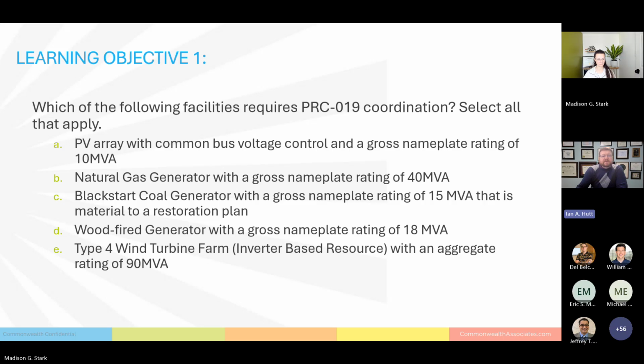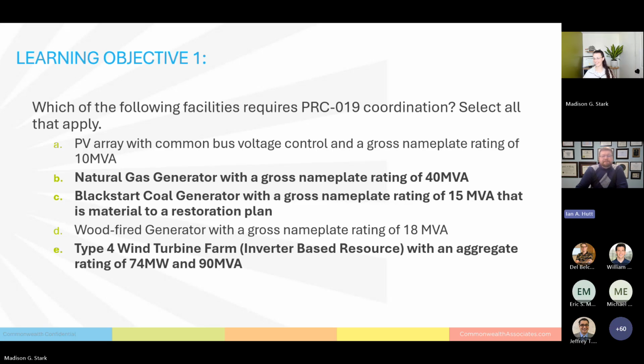All right, answers are coming in, and it looks like we got 37 responses. We'll wait a second here for some other responses. All right, as the answers come in, it looks like the selections are the natural gas generator with a 40 MVA rating, the black start coal generator with a 15 MVA rating, and the Type 4 wind turbine with a 90 MVA rating. Seems pretty overwhelming. That is correct, and it looks like I am an excellent teacher.